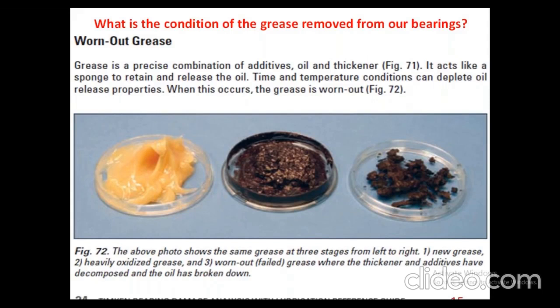hotspot. We always look into the energy conservation law. Whatever energy is input to the system has to come out. If the output is not coming out fully, then the loss will be there. The symptom of loss is the hotspot, which is measured by your infrared thermal imagers. If you see the last one, it is totally worn out. This type of grease is there in many of the textile mills. When you go for an energy audit, I don't say you need to do the grease analysis, but you check the condition of the grease. You find that both the thickener and additives have totally decomposed and the oil is totally broken down. This needs to be replaced right in time. The specialty grease, the polyurea thickened grease, is definitely able to do the job.